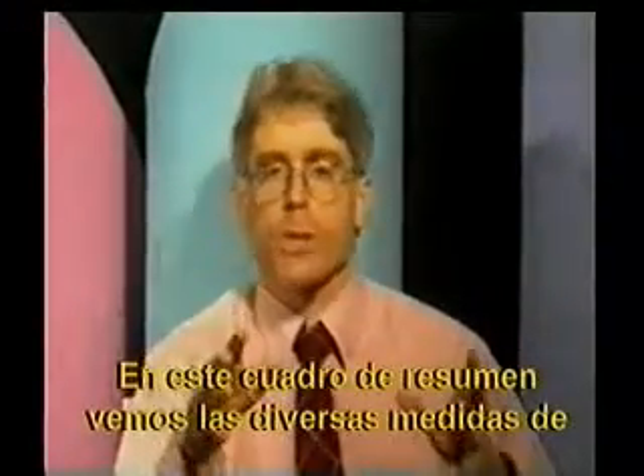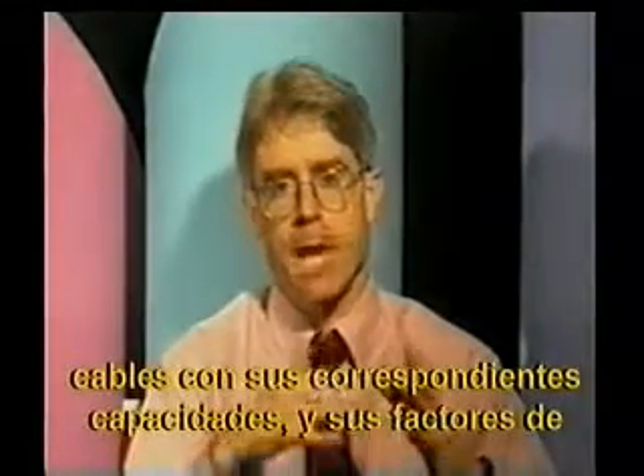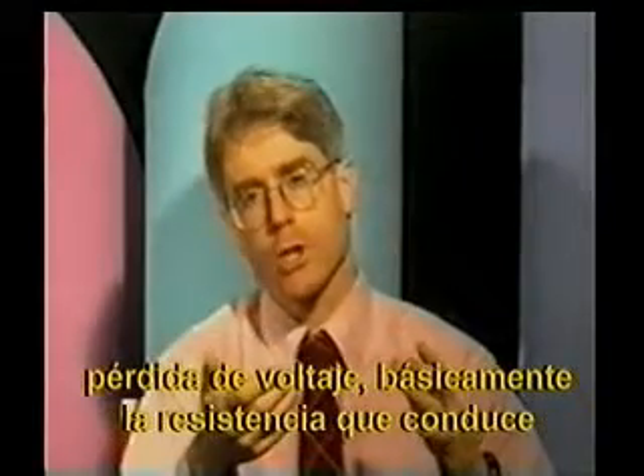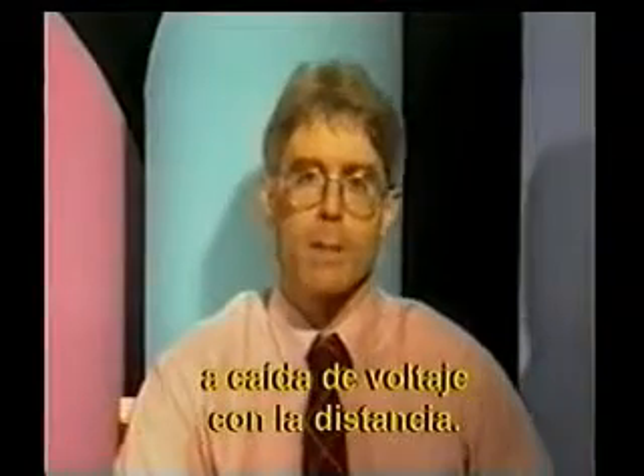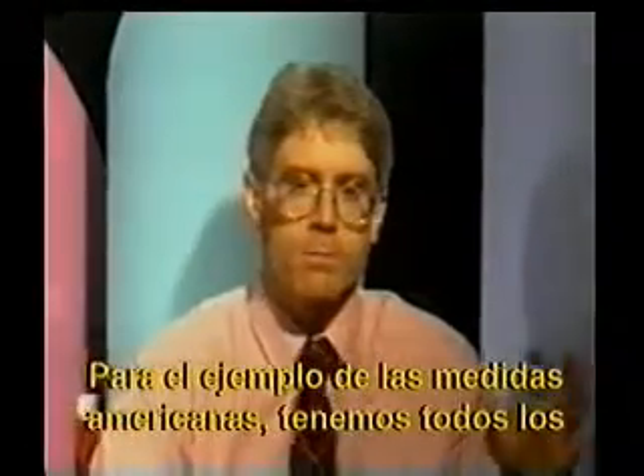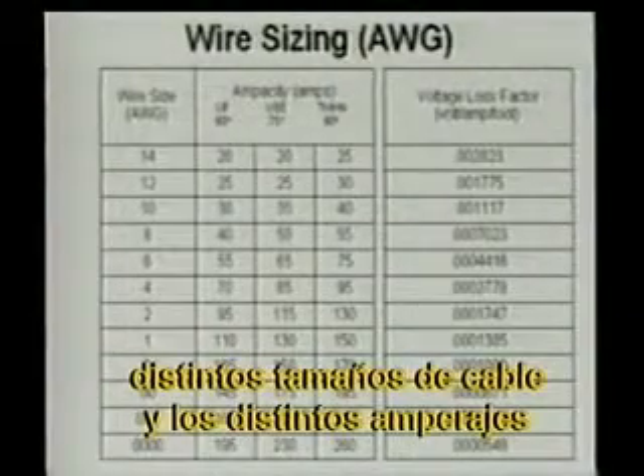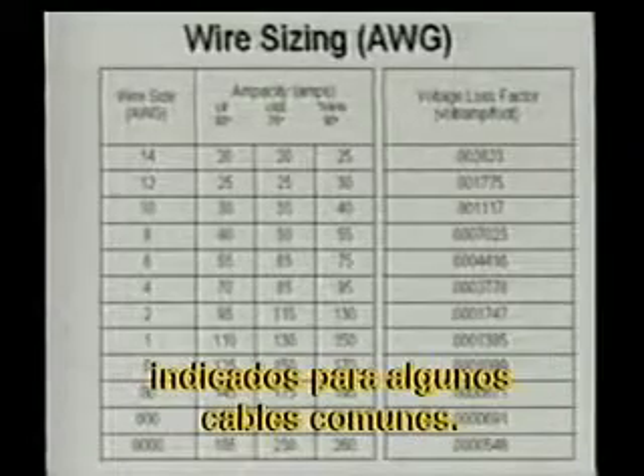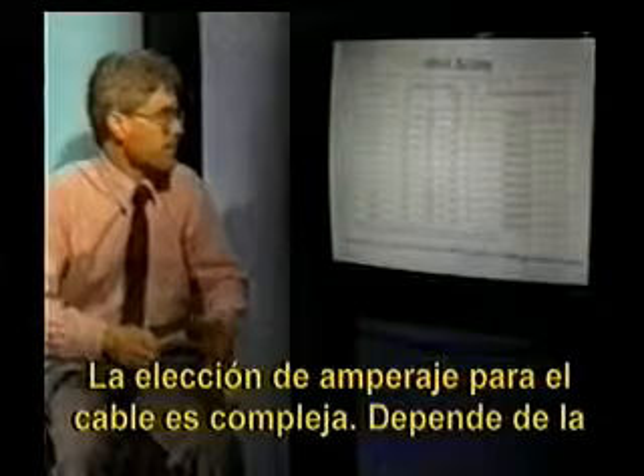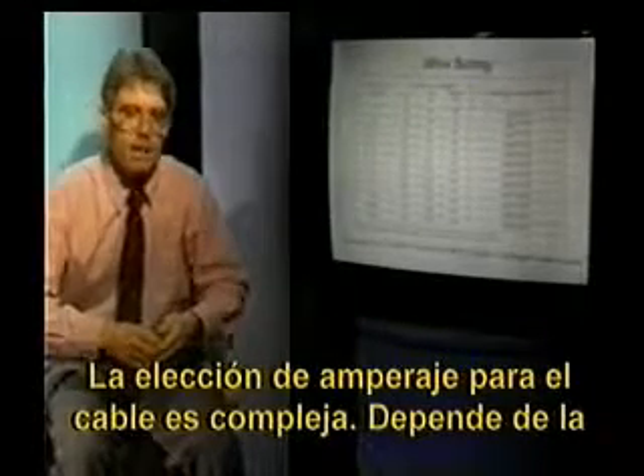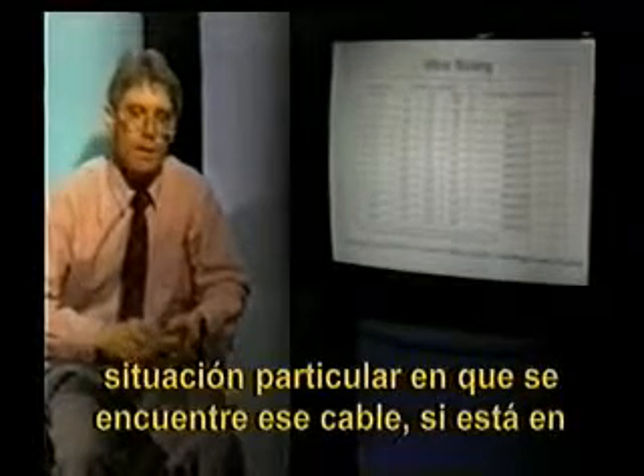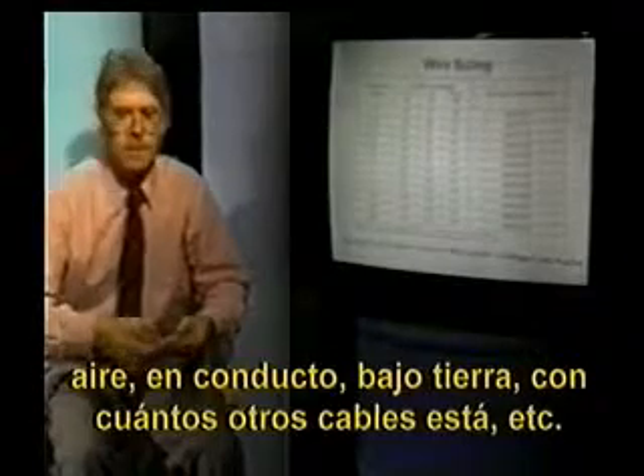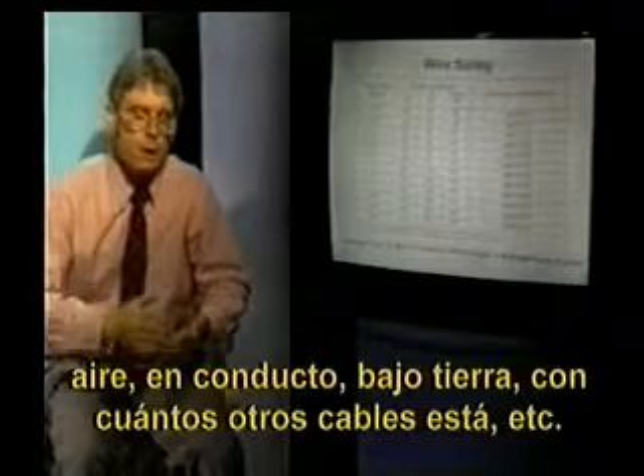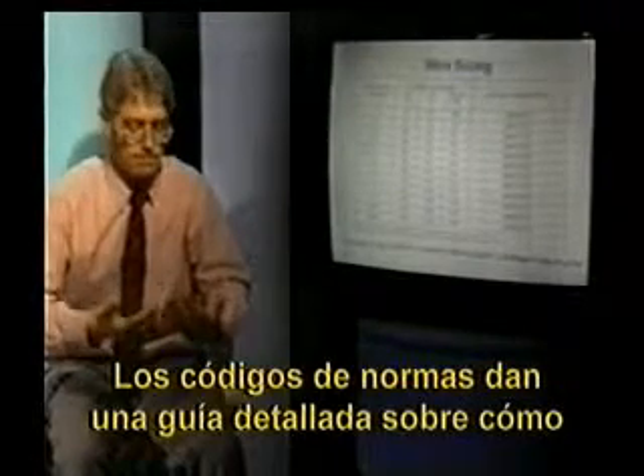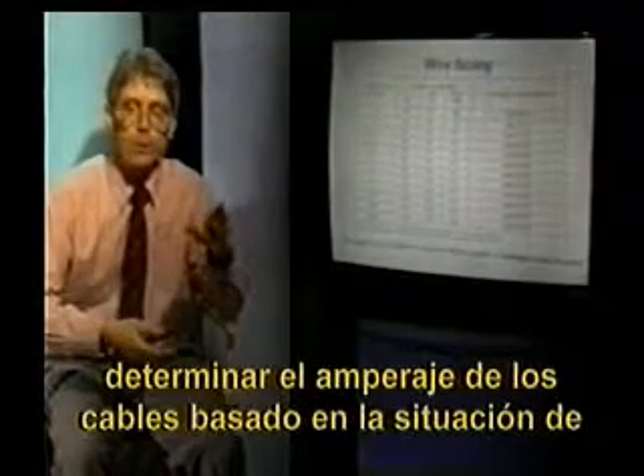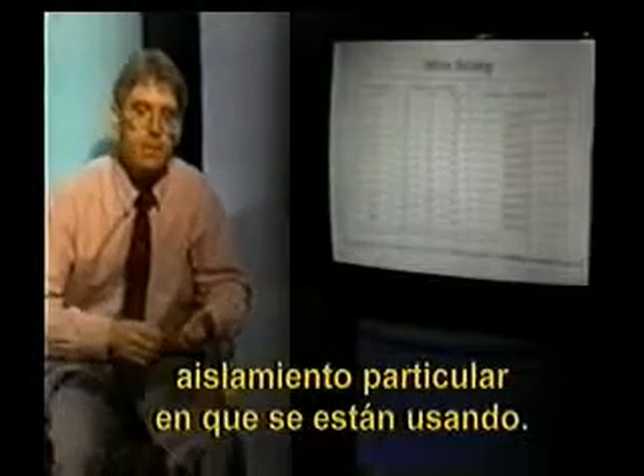We've created for you a summary chart that shows various wire gauges and their associated ampacities and their voltage loss factors, basically their resistance that would lead to voltage drop over distance. For the American wire gauge example, we have all the different gauges of wire, the different sizes, and different ampacities indicated for some different common types of wires. The point here is that choosing the ampacity of the wire is a little bit complex. It depends on the particular situation that wire finds itself in. Is it in air? Is it in conduit? Is it buried? How many other wires are with it? And so on. Code guidelines give a much more detailed guide as to how to determine the ampacity of wires based on the particular situation and the particular type of insulation that you're using.